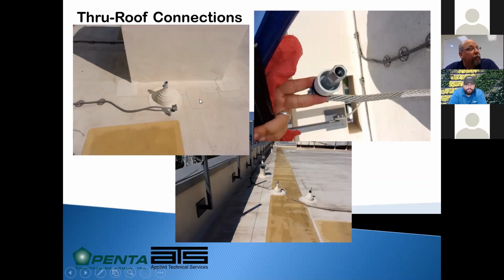And then it was handed over to the lightning protection contractor, and they did a beautiful job on the rooftop, but they never connected the two. They never connected below the roof line to the down conductor. So again, having your system inspected by a qualified professional is very paramount to ensuring that you're getting what you paid for and that it's actually working and doing its job.